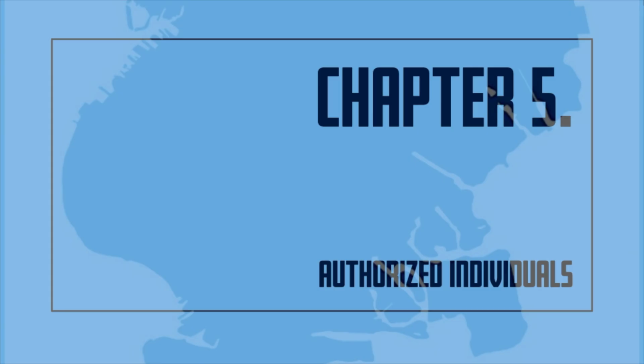Refrigeration operating engineer with the refrigeration Q99 and Q01 licenses, a high-pressure operating engineer, and a New York State high-pressure operating engineer are permitted to perform visual inspections, test notification appliances, perform daily and weekly routine maintenance, and record all inspection, testing, and maintenance results for examination by the fire department.